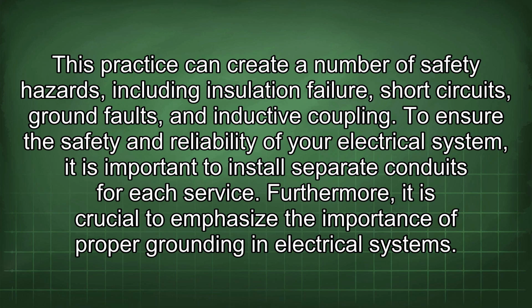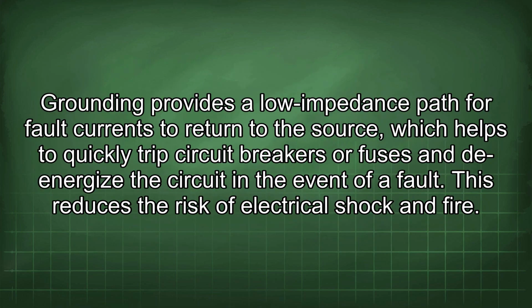Furthermore, it is crucial to emphasize the importance of proper grounding in electrical systems. Grounding provides a low impedance path for fault currents to return to the source, which helps to quickly trip circuit breakers or fuses and de-energize the circuit in the event of a fault.